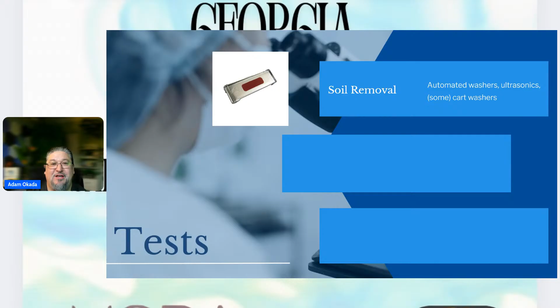Ultrasonics use transducers, which provide the ultrasonic or cavitation action. There are tests specifically for cavitation. A lot of people don't know that your soil removal test, if just placed in the center of the tank, can pass even though there are dead spots in your ultrasonic with no cavitation happening. So you need a test that's actually looking at cavitation specifically.